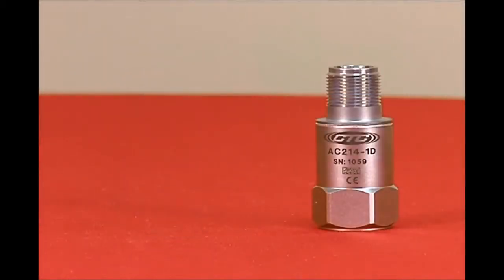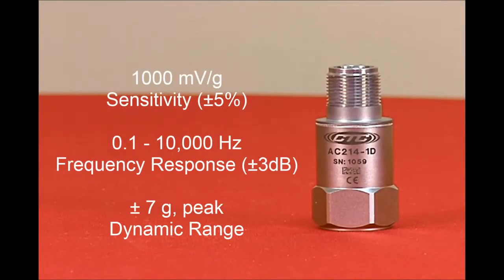The AC214-1D is a 1000 millivolt per G or 1 volt per G sensor with a frequency response from 0.1 hertz to 10,000 hertz, 6 cycles per minute to 600,000 cycles per minute. The dynamic range is plus or minus 7 G's peak.